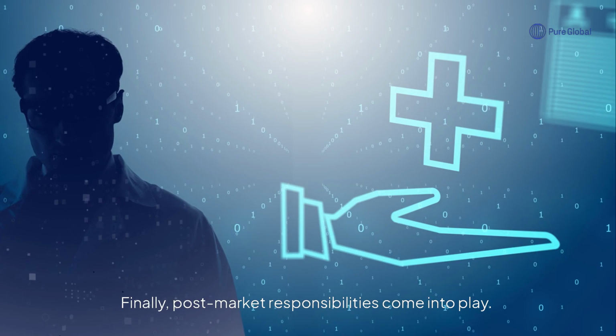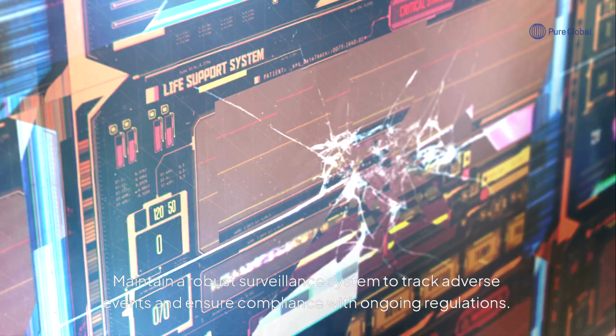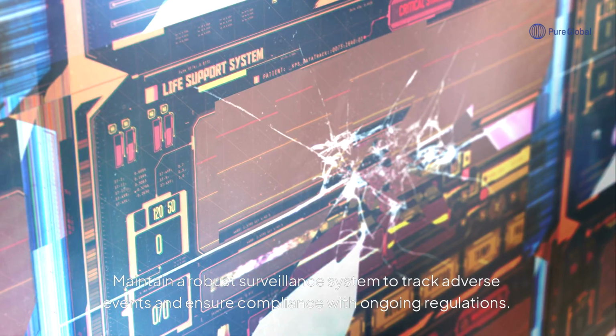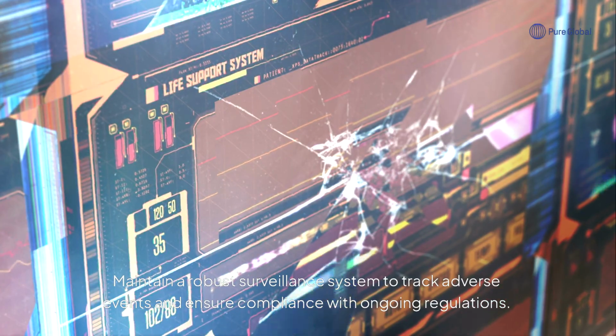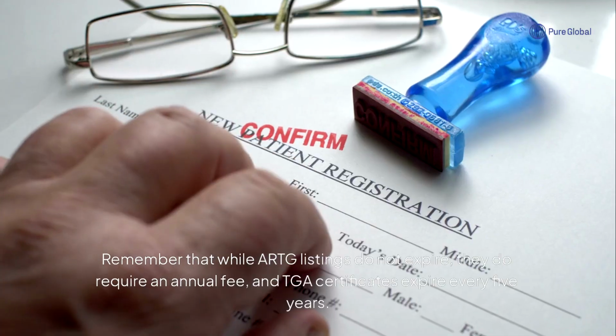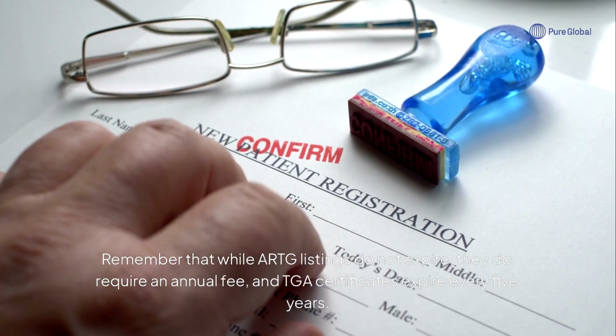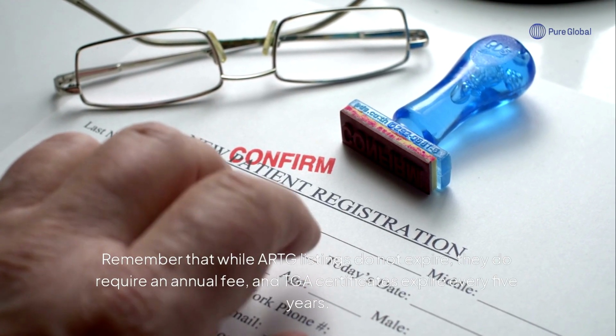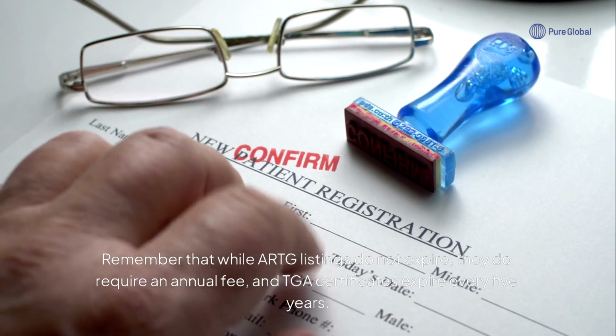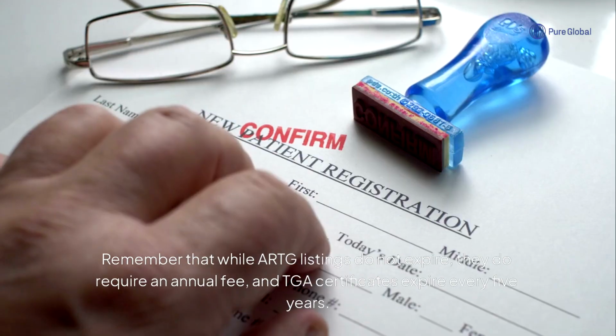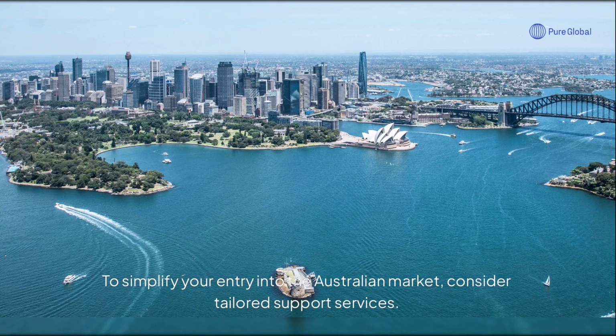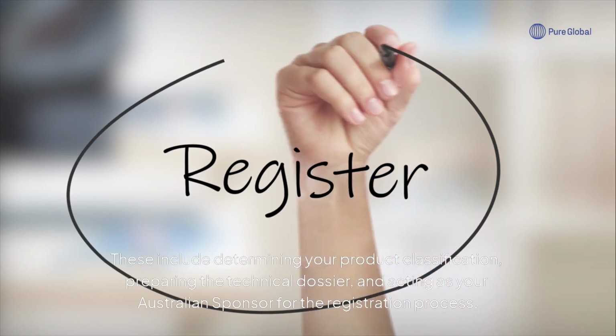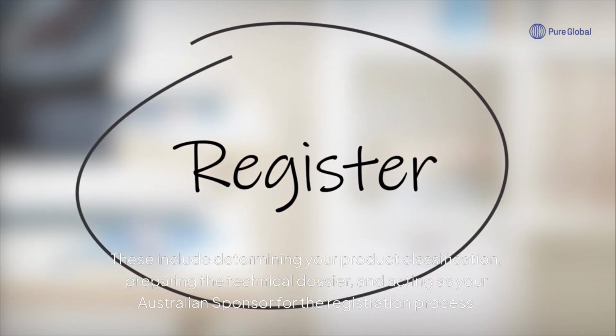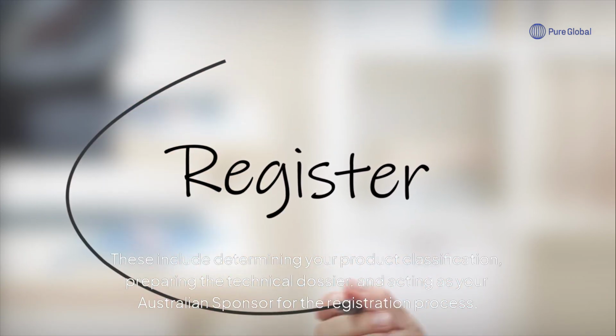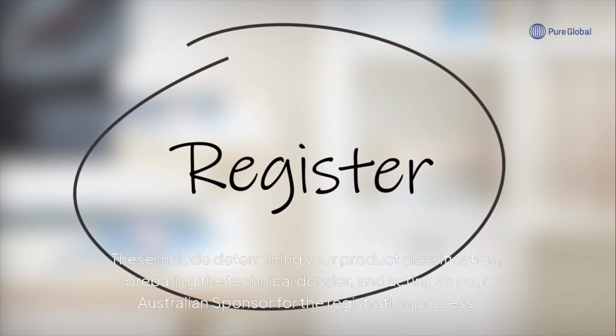Finally, post-market responsibilities come into play. Maintain a robust surveillance system to track adverse events and ensure compliance with ongoing regulations. Remember that while ARTG listings do not expire, they do require an annual fee, and TGA certificates expire every 5 years. To simplify your entry into the Australian market, consider tailored support services. These include determining your product classification, preparing the technical dossier, and acting as your Australian sponsor for the registration process.